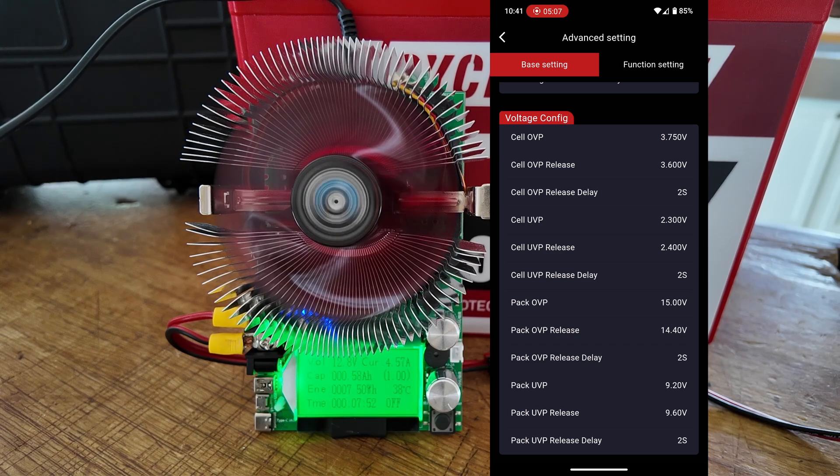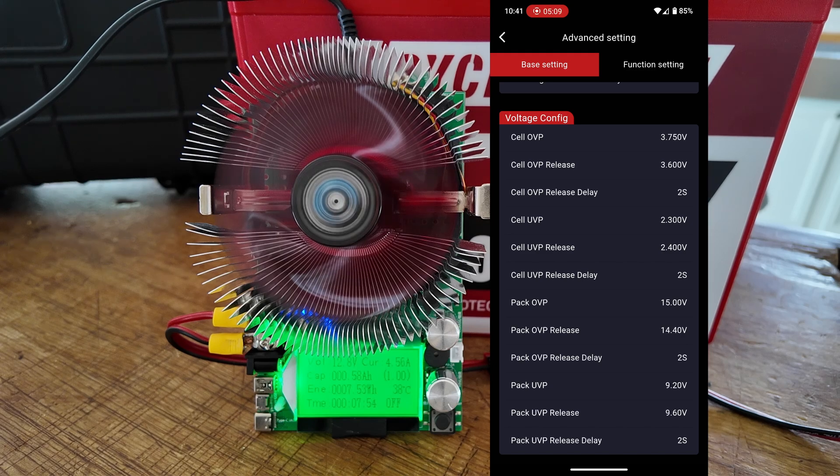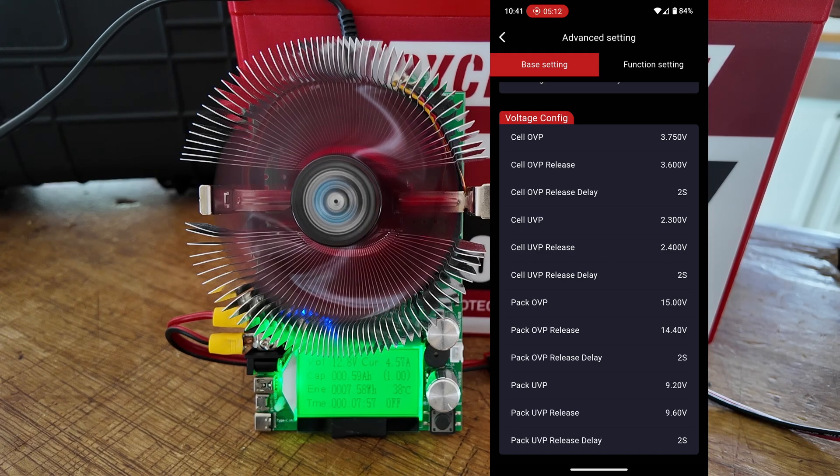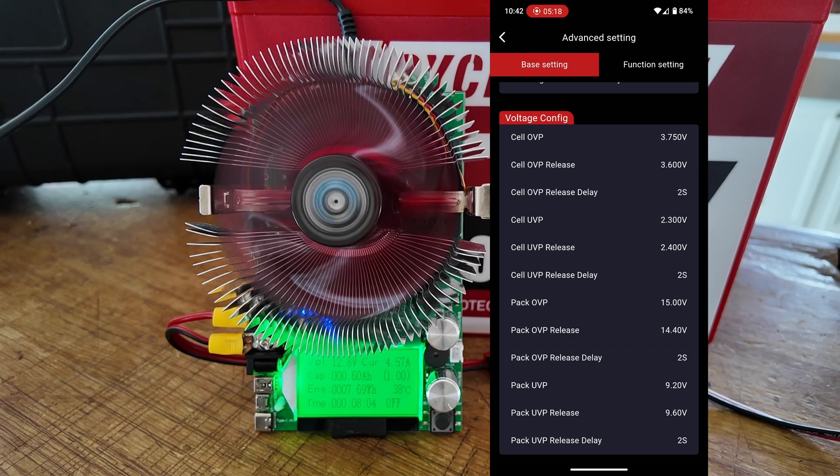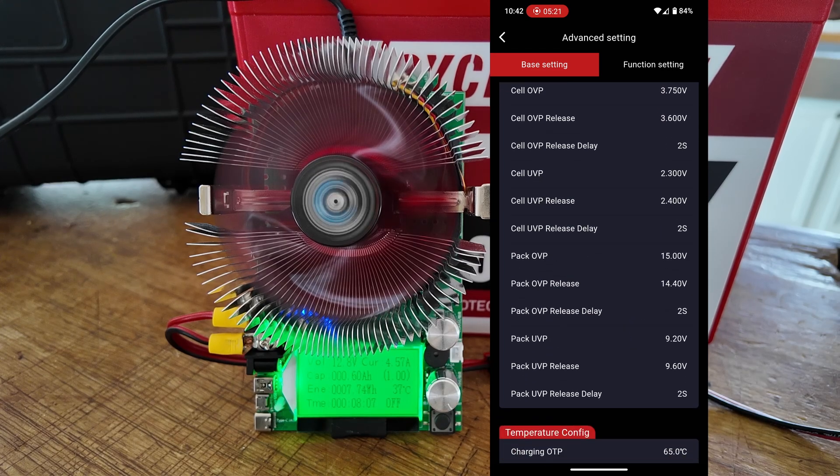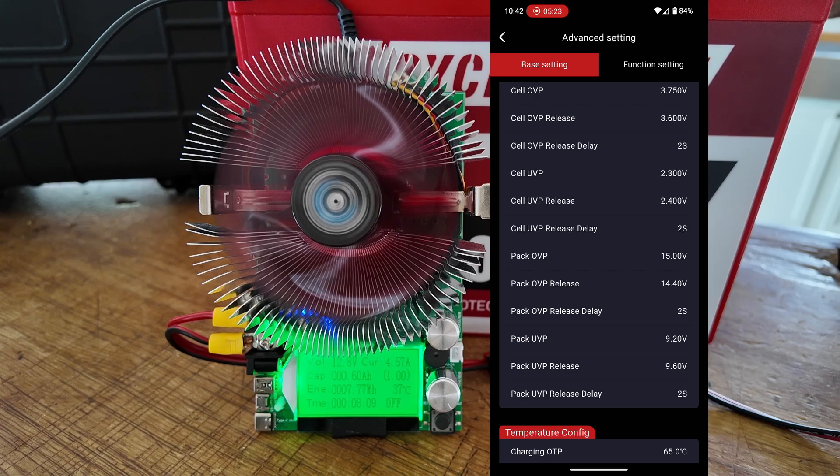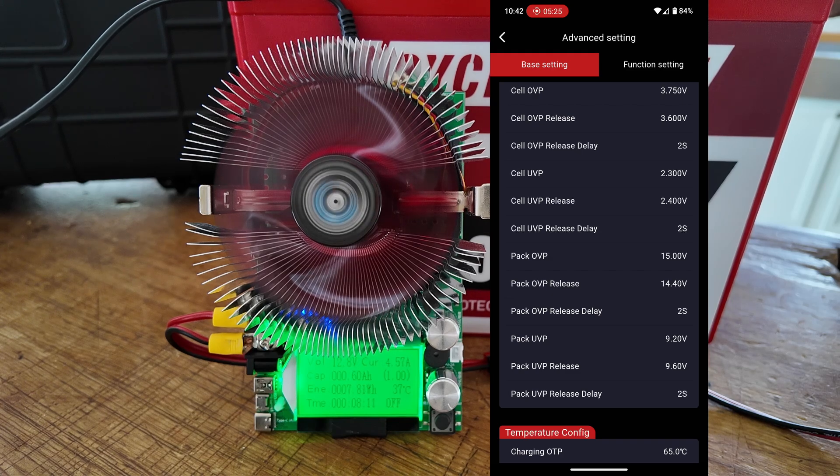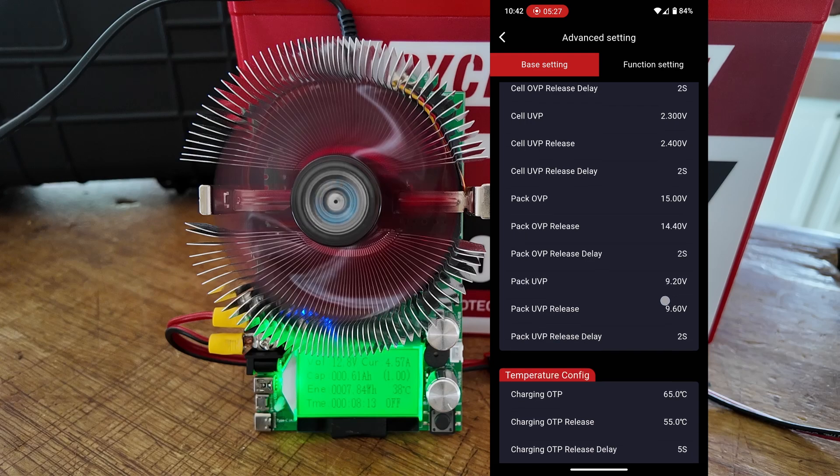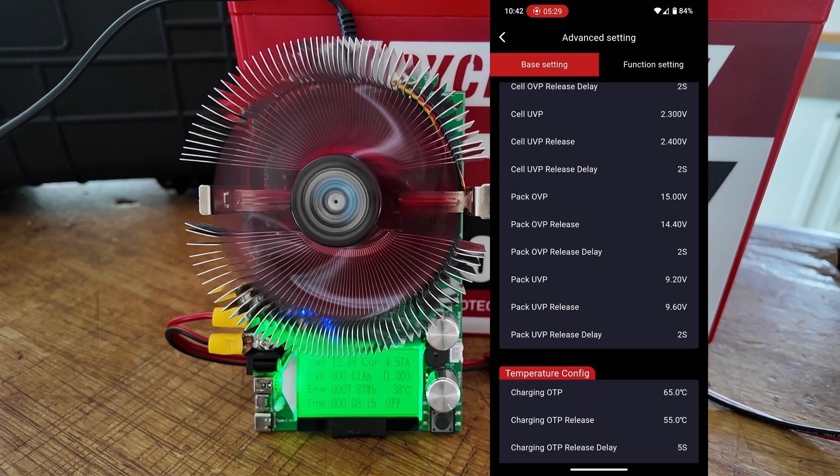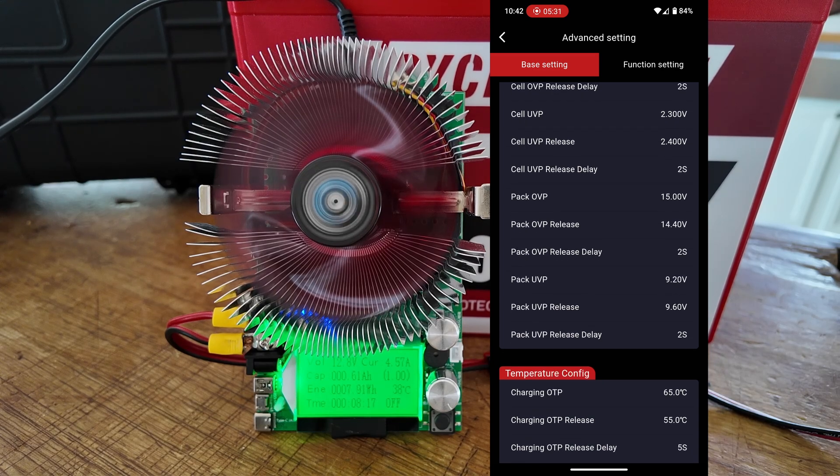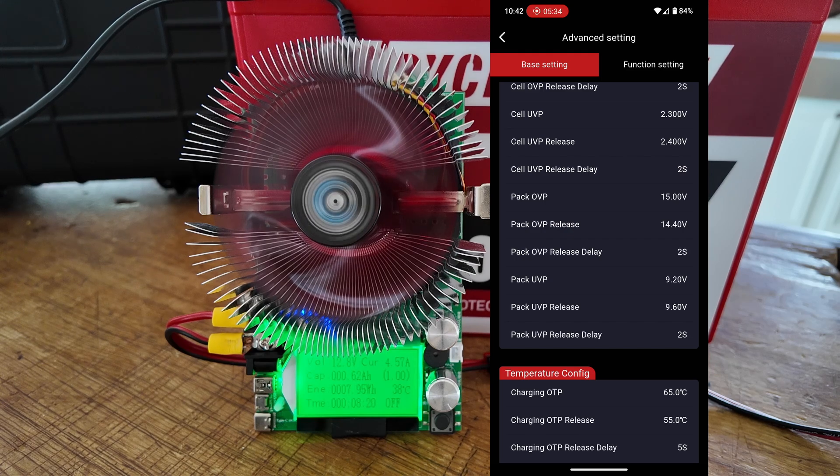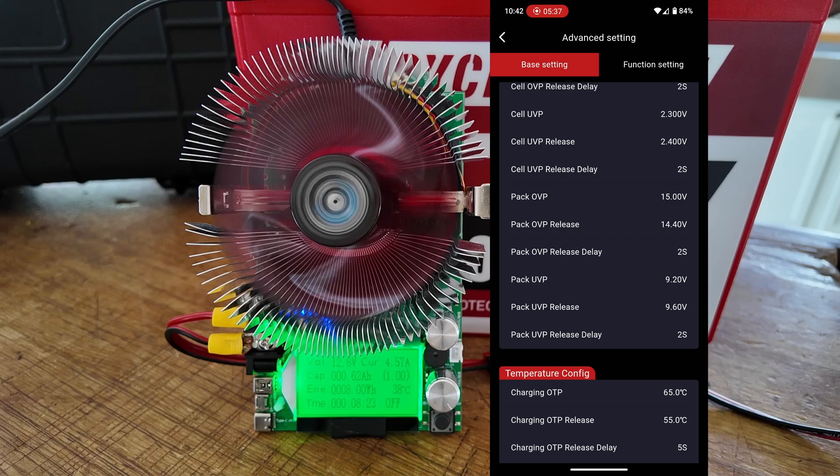Once it gets back below 3.6 volts, it will go ahead and take that hold off and allow you to charge the battery once again. The same thing applies for the under-voltage protection, which is currently set at 2.3 volts, and the under-voltage protection release set at 2.4 volts. We can change the over-voltage protection of the entire pack, which is currently set at 15 volts, and the release is 14.4 volts.